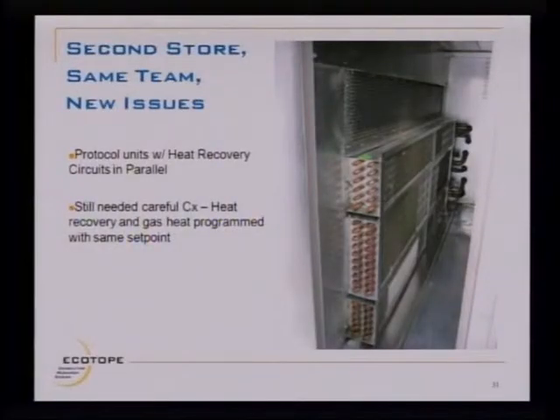But remember that to do domestic hot water from this refrigeration equipment, you're really only going to get that superheat portion of the refrigeration. You can't condense, since you're trying to heat the water up to 120 degrees, you're not going to condense that refrigerant with 120 degree water. So you're only getting a portion of what's there. The other 3 units they brought up with 3 independent coils. This is looking inside the main air handling unit on the roof.